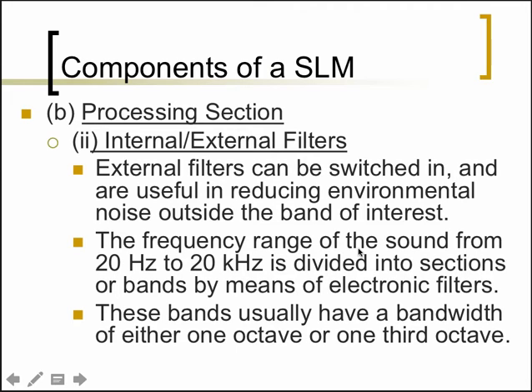So again, the processing section has internal and external filters. External filters can be switched in, and as I said, will help reduce the environmental noise outside the band of interest. So when one is calibrating 1000 hertz, you don't want any humming noise from the light or noise from the HVAC system to influence your calibration. So it would be wise to use the 1000 hertz filter in your sound level meter, so your readings are not influenced by the energy at frequencies outside the 1000 hertz that you're testing.